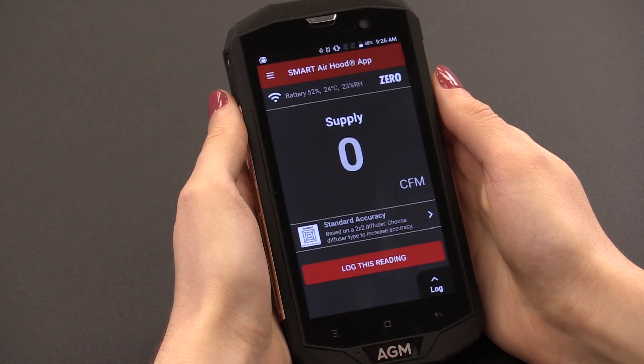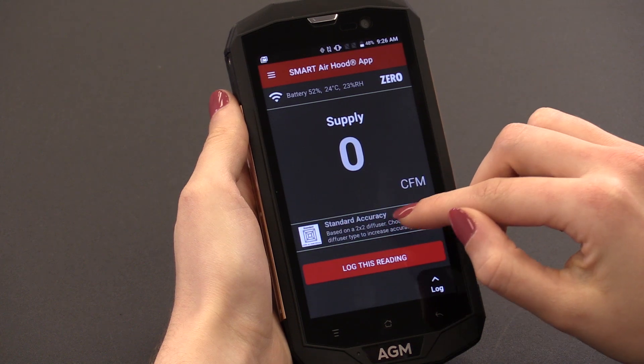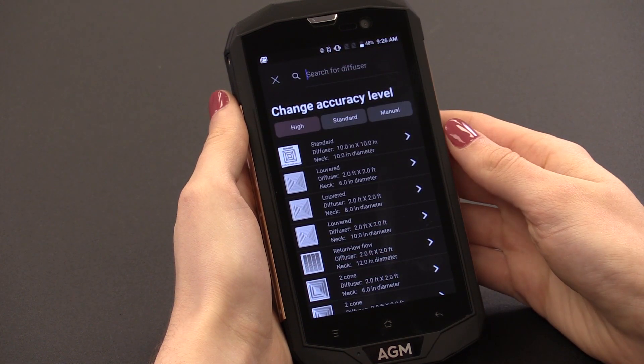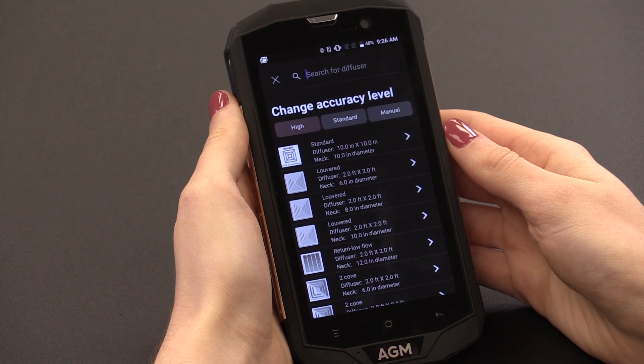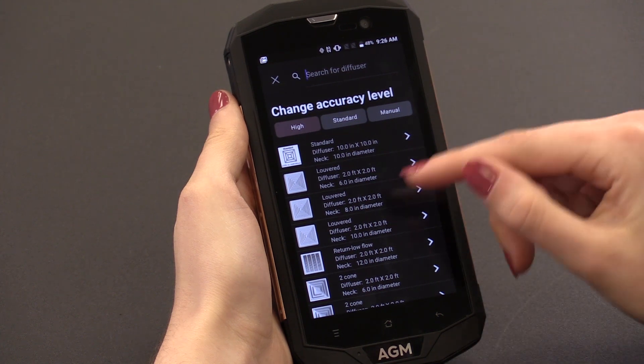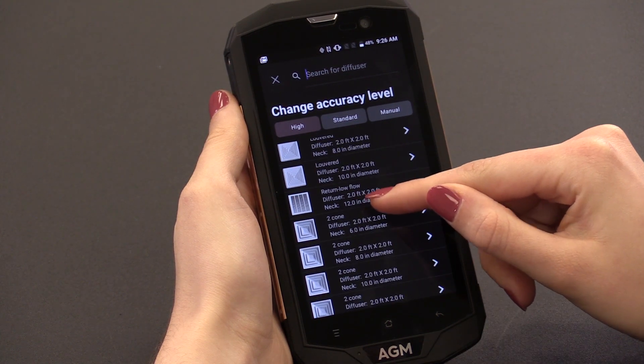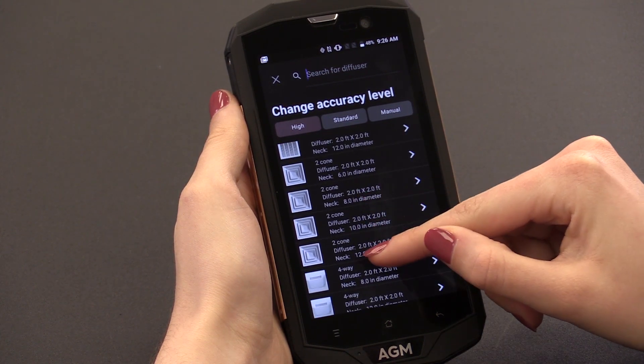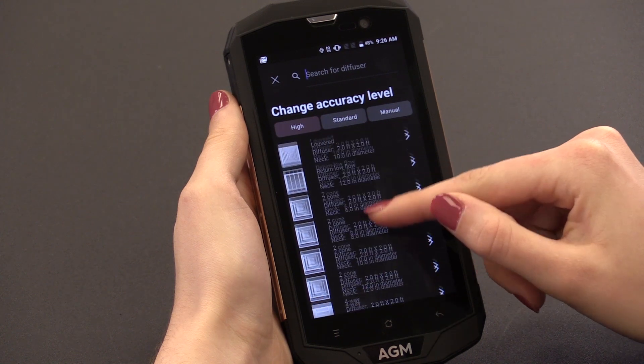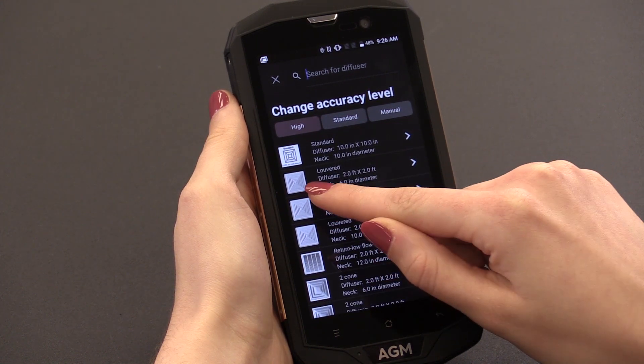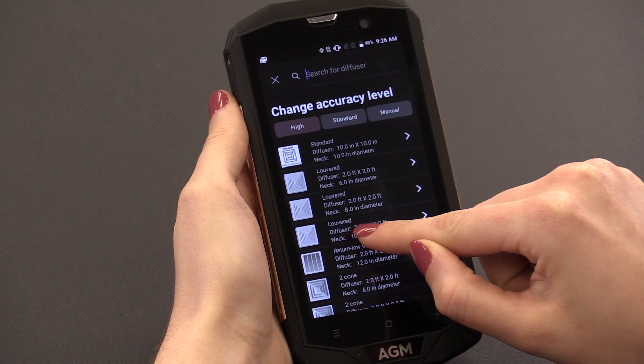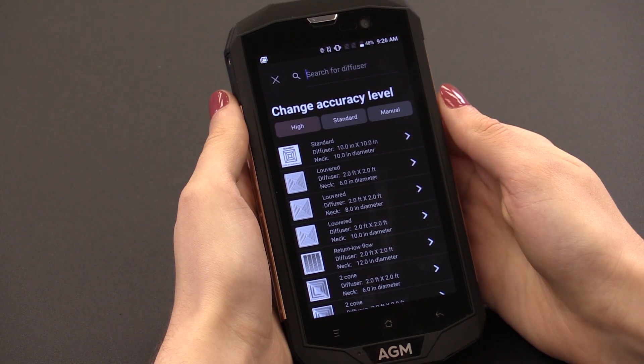The Smart Air Hood app has three main options for accuracy with diffuser selection: high accuracy, standard, or manual. Our high accuracy option is rated to plus or minus 3% of reading, making the Smart Air Hood one of the most accurate airflow hoods in the market. This level of accuracy is attained because Dwyer has calibrated each Smart Air Hood to match the profile of individual diffuser styles. Simply look for the picture or name of the diffuser style you are measuring and select that option to measure airflow of that diffuser style.